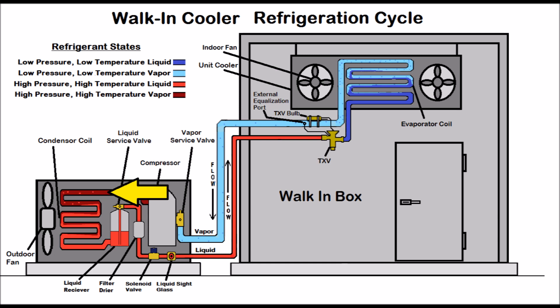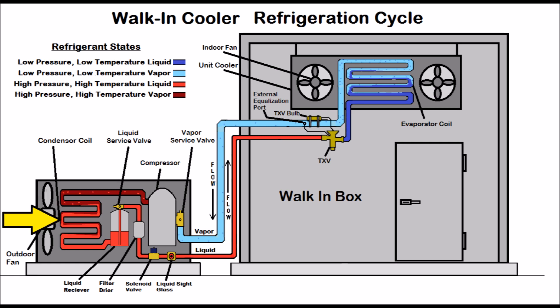The refrigerant rides the discharge line until it goes into the condenser coil where it's rejecting heat to the outside air. It starts rejecting enough heat until it turns into the saturated state — that's where liquid and vapor both exist at the same time. That's shown by the dark red and light red colors in the condenser coil. That saturated state is where most of the heat is being rejected.